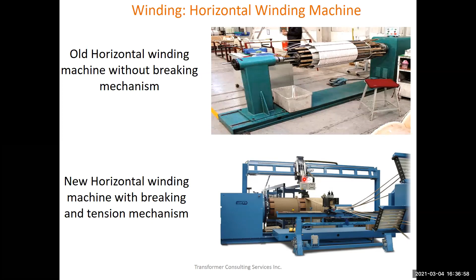Now, you may have a question: why is it more important to wind this conductor much tighter against the cylinder? The reason is, when you put the transformer into service, if the transformer experiences repeated through fault, fault meaning the fault current. When the fault current gets inside the transformer, the current creates a force, which is called short circuit force. There will be a huge short circuit force inside the transformer. If it is loose, the conductor will shake inside the transformer, and when it shakes, it will cause the failure.